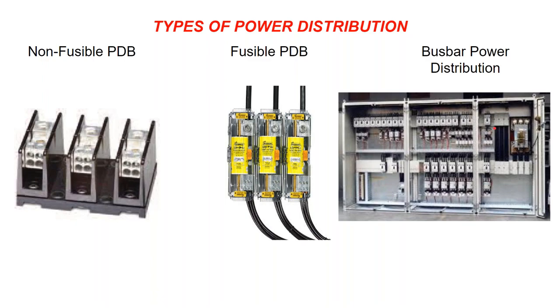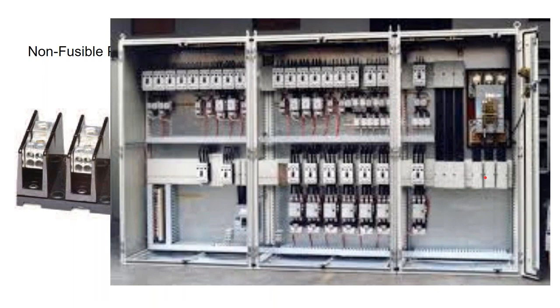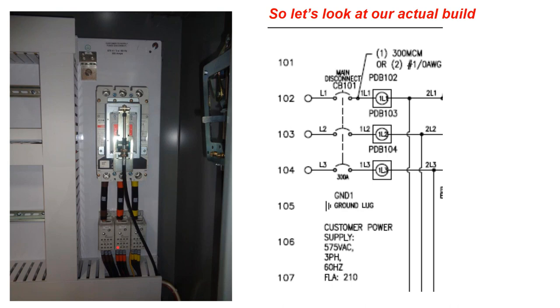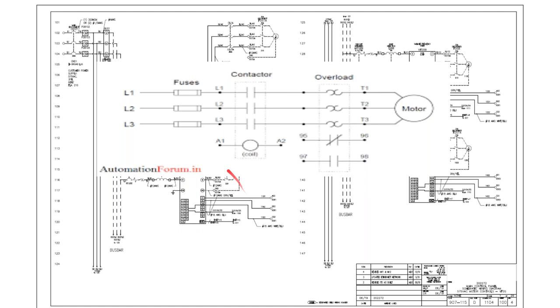Another way to distribute power is with a bus bar. Here the main disconnect feeds a horizontal bus, and all the circuit breakers and motor starters can connect right to that bus — convenient when you have a lot of power and high amps. In the actual build you can see the main disconnect, the power distribution block, the ground lug, the circuit breaker disconnect with the cable going to the handle, and the power distribution.